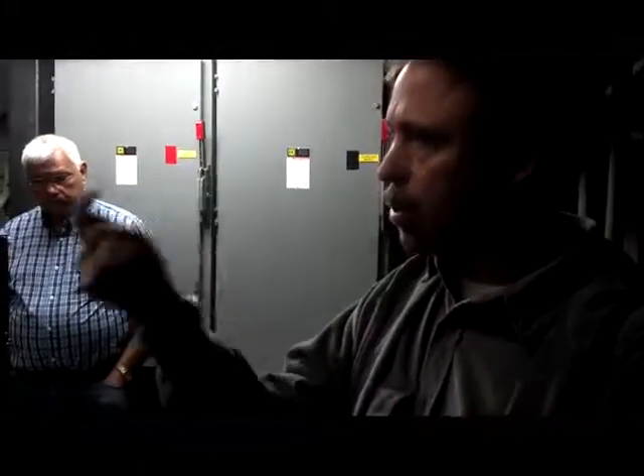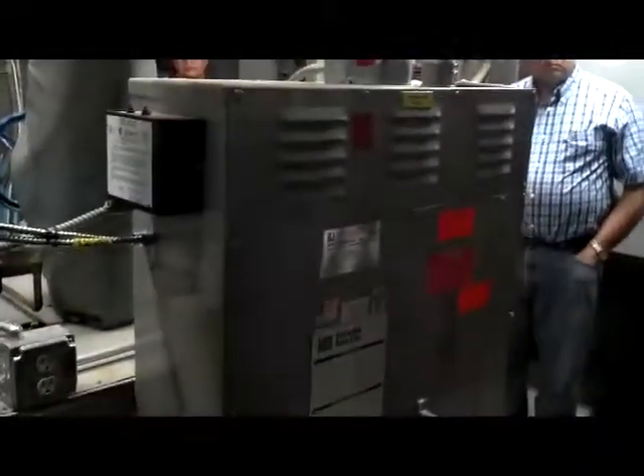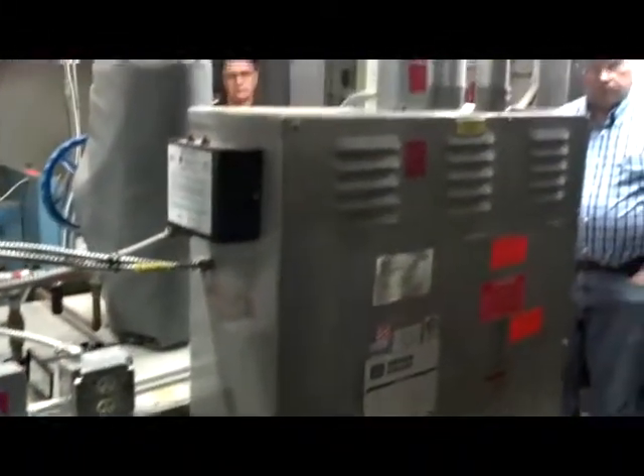So what I'm going to do is, if there's a well, if not a well, we'd be able to put a surface-mounted sensor on that tank that would go back to the same PLC. It's not going to do anything but give you an alarm saying, hey, your condensate's going up. If it's creeping up, we might not have 5 traps bad, we might only have 1.